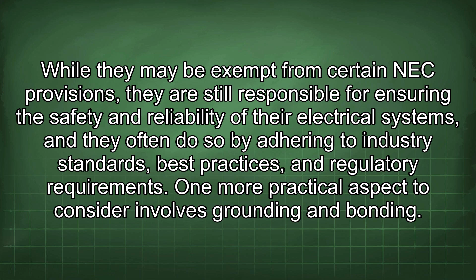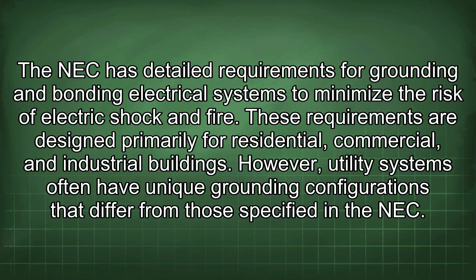One more practical aspect to consider involves grounding and bonding. The NEC has detailed requirements for grounding and bonding electrical systems to minimize the risk of electric shock and fire. These requirements are designed primarily for residential, commercial, and industrial buildings. However, utility systems often have unique grounding configurations that differ from those specified in NEC. For example, utility substations may use a grid of interconnected ground rods and buried conductors to create a low-impedance ground path. This grounding grid is designed to dissipate fault currents quickly and minimize the risk of ground potential rise, which can be hazardous to personnel and equipment.